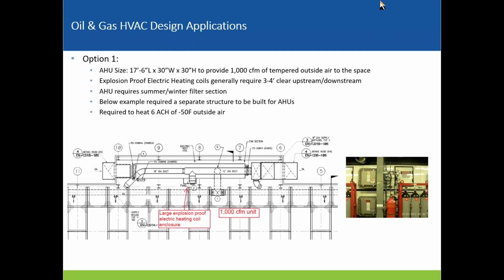Also, I should note, the AHU did require summer and winter filter sections on either side of the heating coil, making it even larger. You don't want to have the filter upstream of the heating coil frost up in the winter, but we also don't want to have a bunch of dirt and dust and debris come into the heating coil during the summer months. So you have to swap the filters out basically on a 6-month cycle.